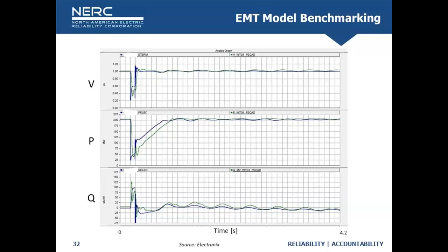Another good example of the growing need for electromagnetic transient modeling is the whole concept of weak grids, or low short circuit strength conditions. We're headed towards a grid where we're seeing at least pockets of low short circuit strength, on the order of a short circuit ratio of somewhere between less than 5, less than 3, less than 2, in some cases less than 1.5. So we're not saying that the whole grid is going that way. We still have a large amount of synchronous machines. We don't see North America headed towards a quote-unquote inertialess system or anything like that. But we definitely have pockets of very low short-circuit strength.